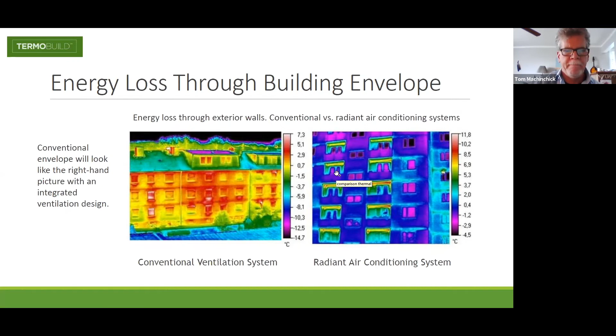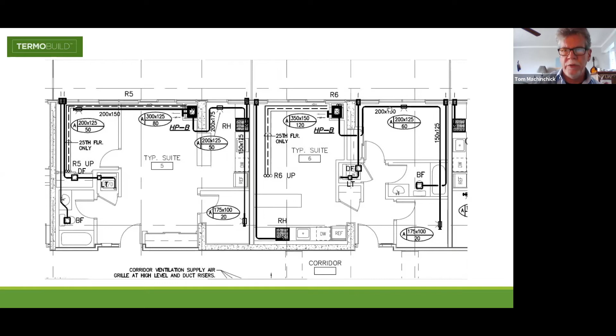With regard to cost savings and cost reductions of a building, this is a diagram of a standard condominium room. You can see that this building has ductwork along the outside perimeter to maintain comfortable temperatures. Now let's move to the next slide and show you what happens with an integrated ventilation design. Our ducting moves along this corridor wall with a vent here, but these perimeter ducts can be eliminated.